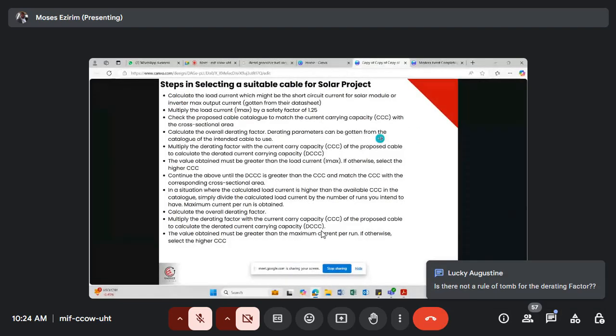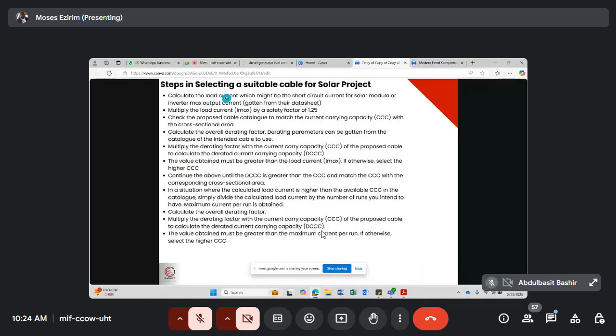Now this is a cable. You can see this is the conductor, this is the insulation, this is the armour, and this is the insulation. All right, now let's move on. Now let's see selecting a suitable cable for solar projects. Now listen attentively. These are the steps. Calculate the load current, which might be the short circuit current for the solar module or the array current.